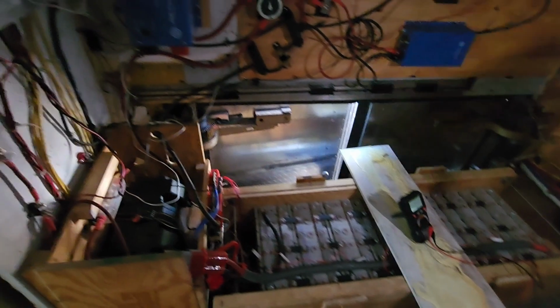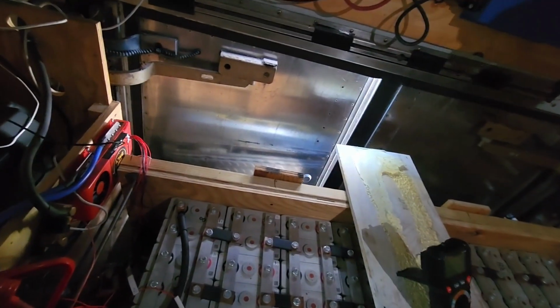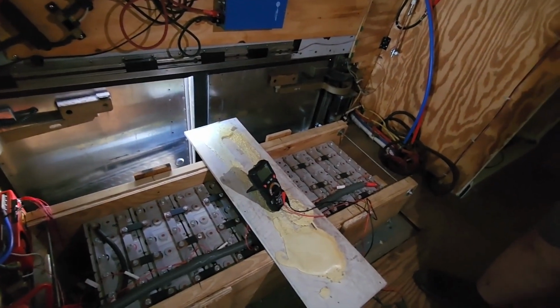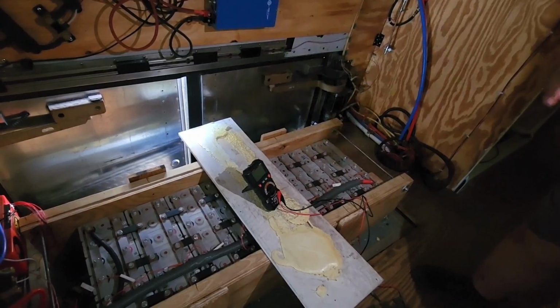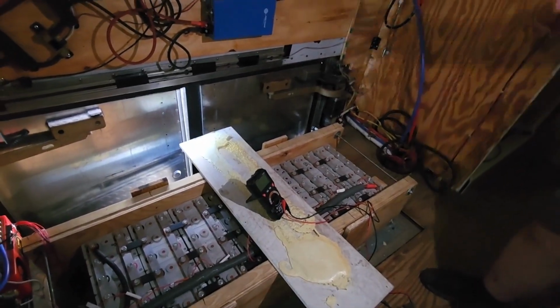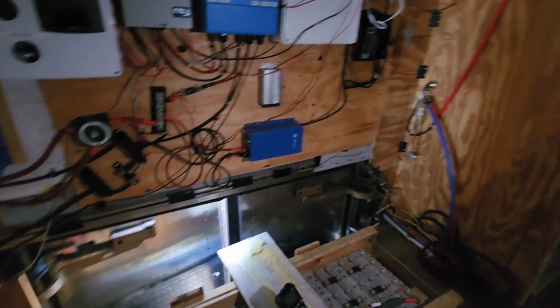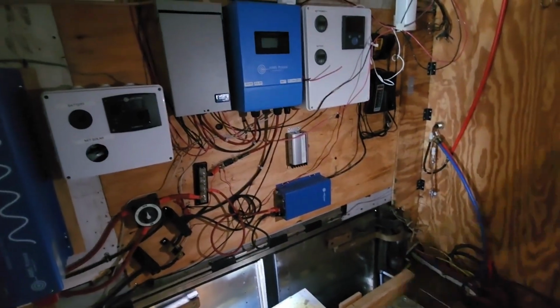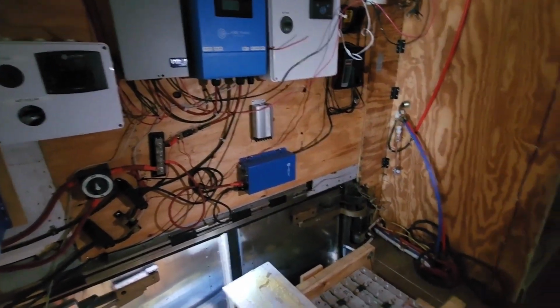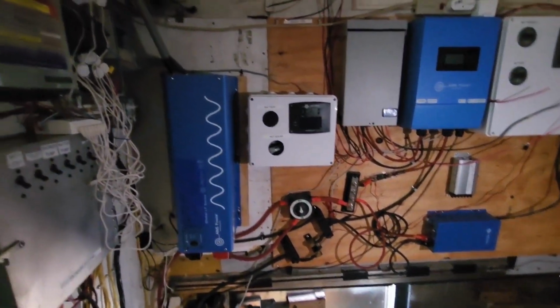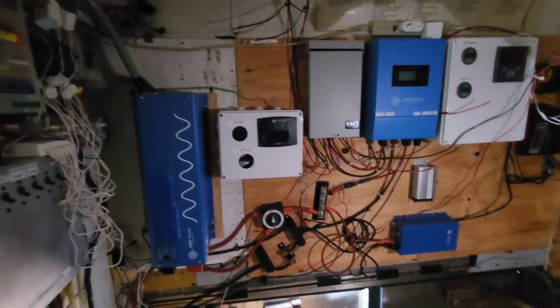So what's happened is my BMS is protecting the battery bank because of this voltage imbalance, and it won't let me run power. It's essentially keeping the system shut down completely, it can't run anything, even 120 volt loads. It's totally locked down, protecting the amperage available on this bus, because I've set my inverter charger to battery primary with shore power as backup, so if the battery is down, shore power is down too.